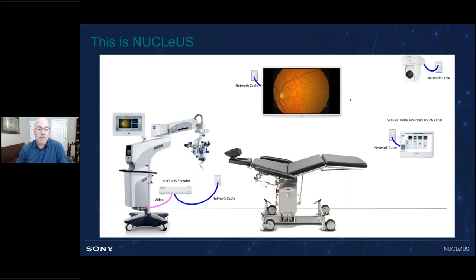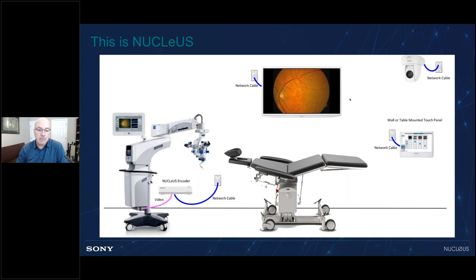The touch panel can live on the nurse desk, it can be mounted on a wall, or if necessary, it can be eliminated altogether and the entire user interface can be controlled from any web browser. For example, the nurse computer that has Internet Explorer or Chrome can have a tab open that completely controls Nucleus. We can also automate the recording process, so the recording begins as soon as the intervention starts, or with the touch of a foot pedal.